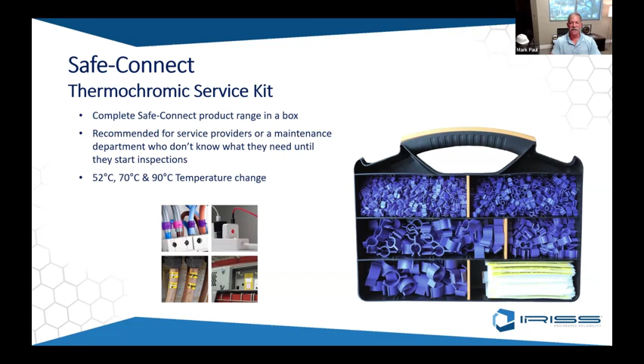This next video shows a thermocouple that is underneath a thermochromic clip. As you see on the meter on the far left, when I start the video you'll see the temperature start to rise. When it gets up to around 70 degrees, it'll start changing color. Then you'll see the temperature come back down, and that clip stays locked in at the lighter colored pink.